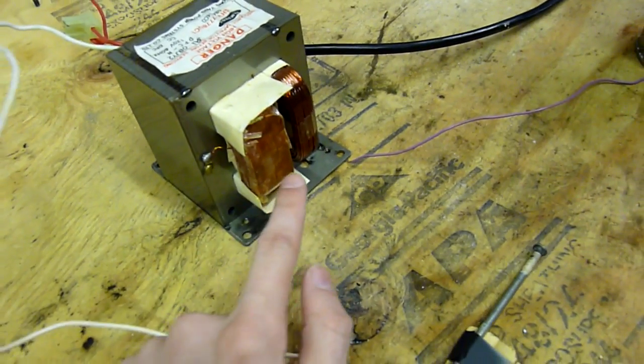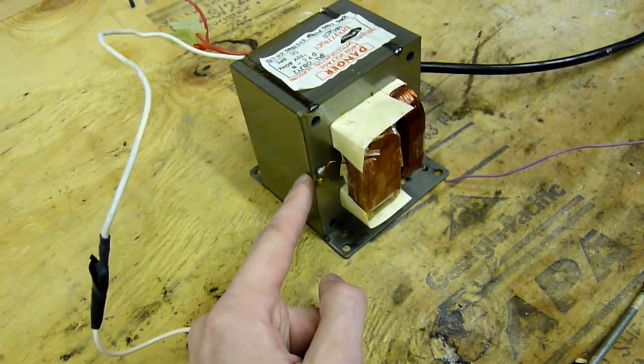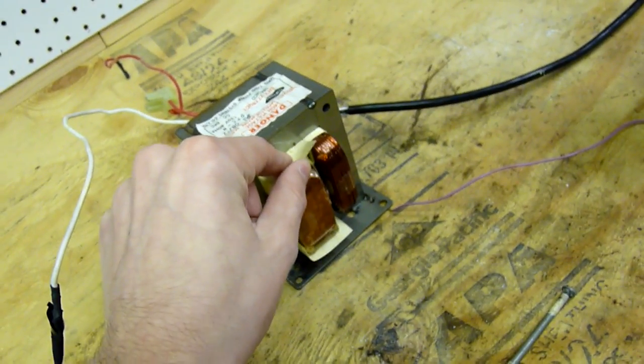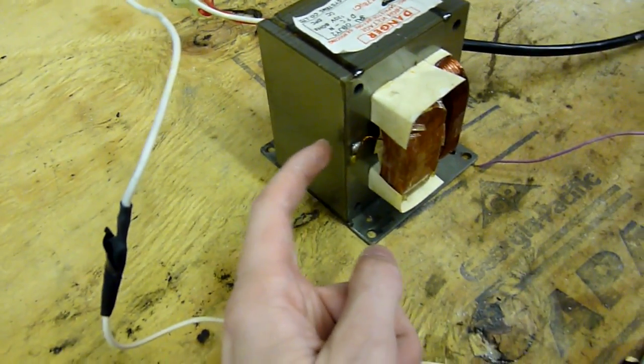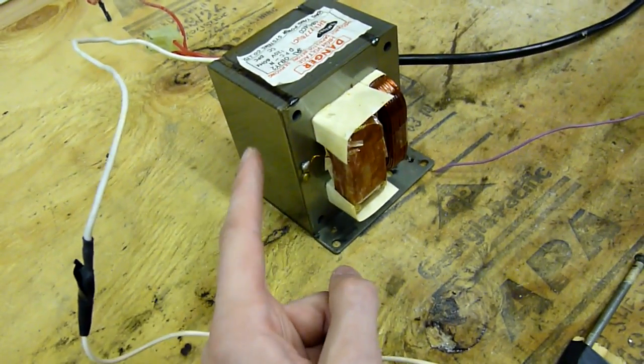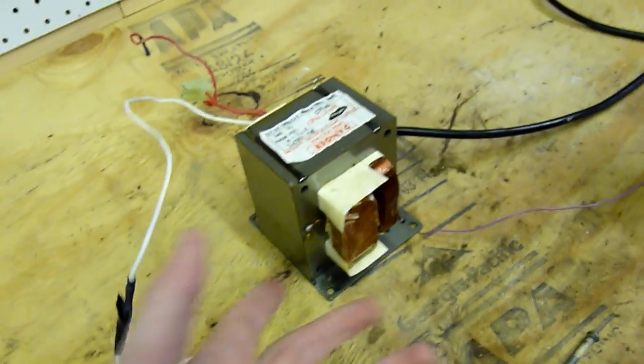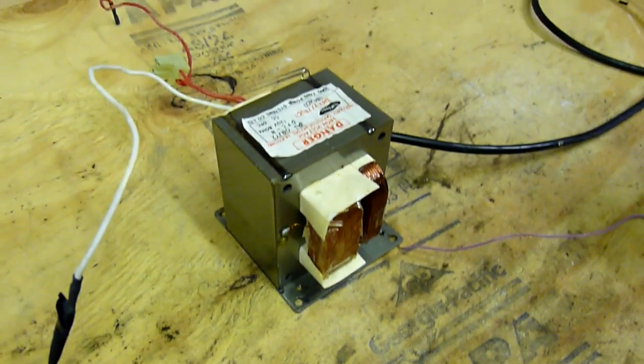So, for instance, between this little enameled wire and the case, there would be about 2,000 volts, which is why they have this big, thick piece of plastic here. But the inside between here, the inner windings and the case is a lot less, because the first turn is only at, like, 1 volt. These are about 1 volt per turn, as I've mentioned in a previous video.